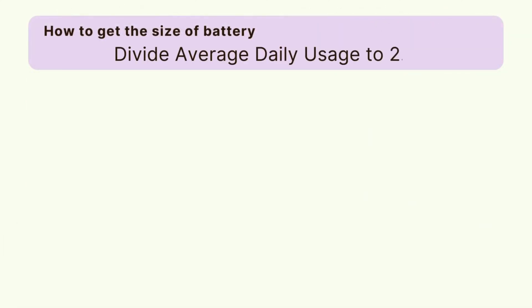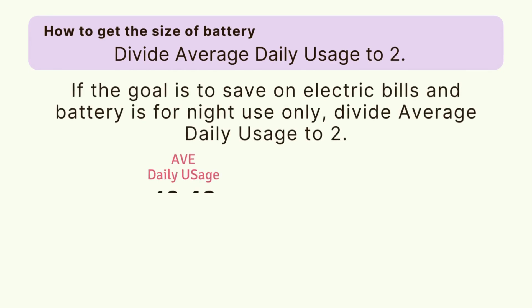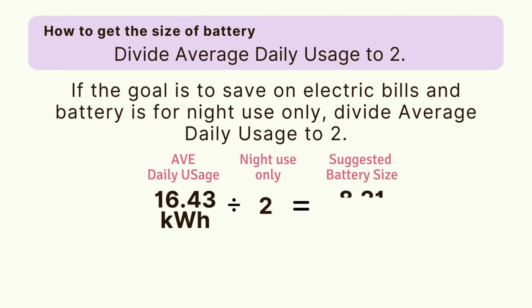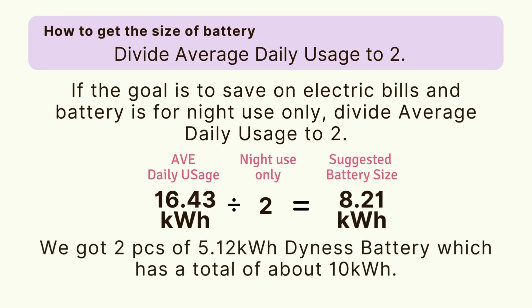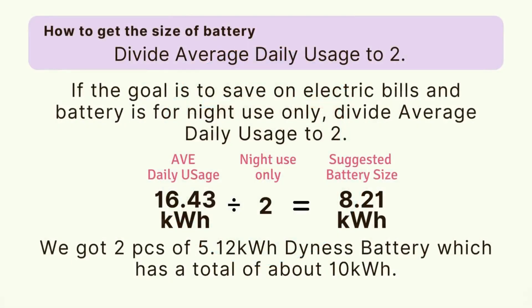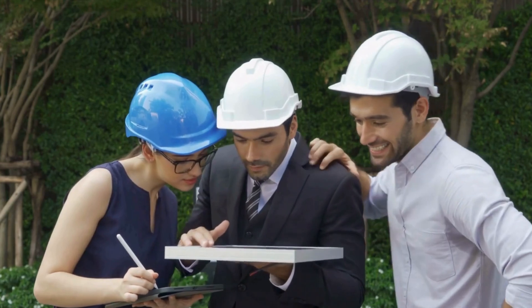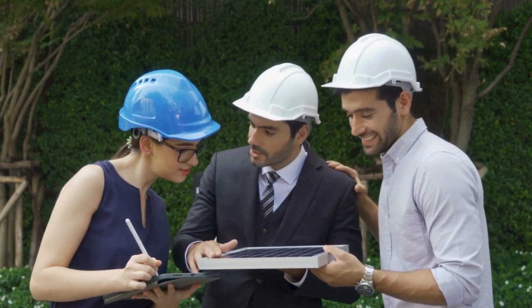For the battery, since our goal is to use it at night and power outages are rare in our area, we simply divide our average daily usage by 2, giving us 8.21 kilowatts. Since we were eyeing Dyness battery, the closest size is 10 kilowatts, so we got 2 pieces of 5.12-kilowatt batteries. The reason we chose two instead of one 10-kilowatt unit is redundancy — if one breaks down, we still have the other.